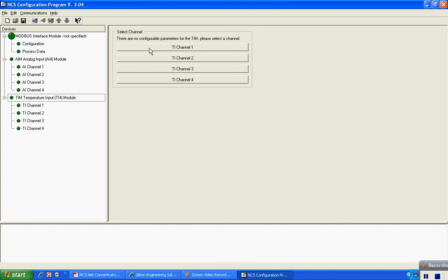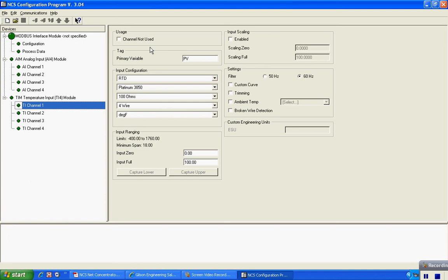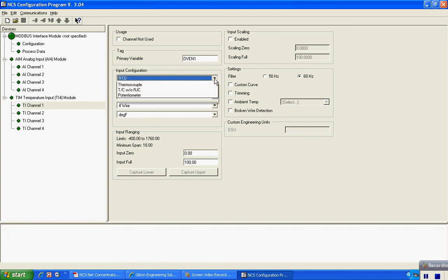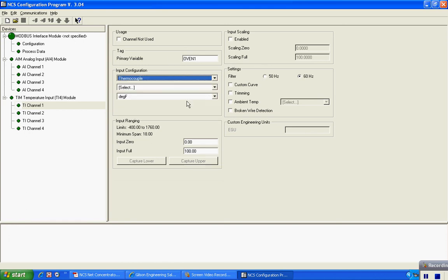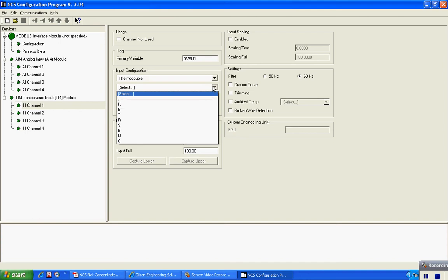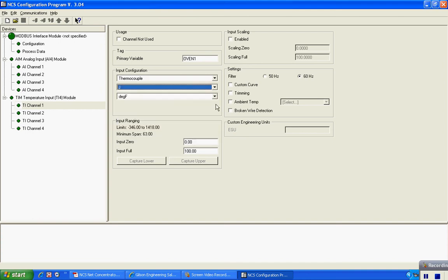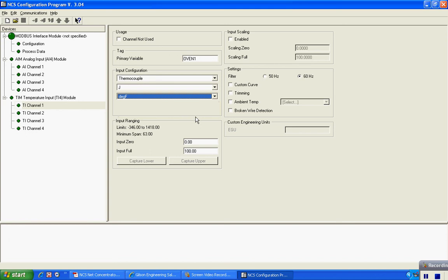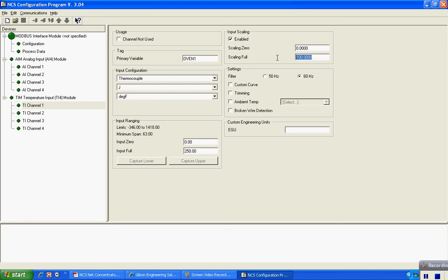The same procedure for channel configuration as we've done before. We can tag each input. We'll call this oven number one, and in this case I have a type J thermocouple input. So I select thermocouple, type J. I want it in degrees F, and in this case it's a 0 to 250 input. I can do the same thing for my scaling, enable 0 to 250, and also put my engineering units of degrees F.